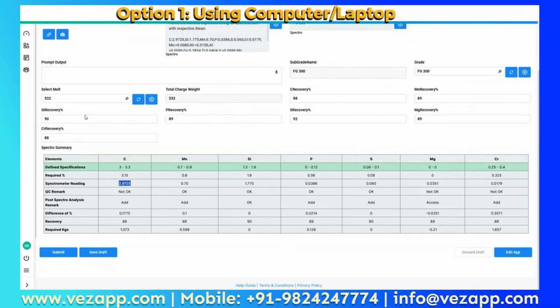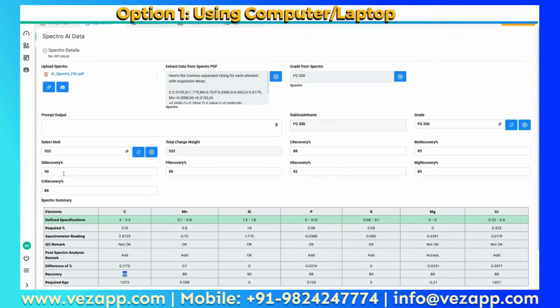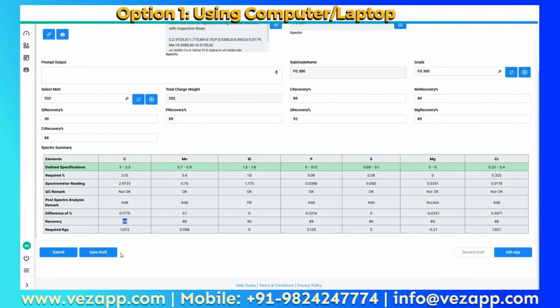Now it automatically calculates the difference of the percentage, and based on recovery as well as the charge mix material we have, it suggests what amount of carbon or manganese or silicon we need to add further. Now let's say 88 is the recovery.